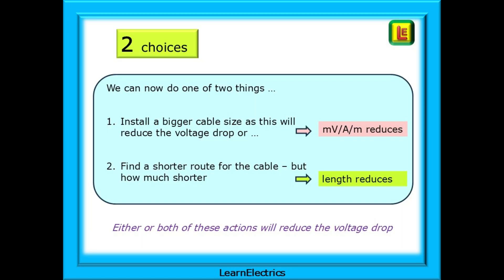We have two choices in order to find a solution. We can do one of two things. Either install a bigger cable size, as this will reduce the voltage drop, say from 4mm cable to 6mm. A bigger cable size will reduce the MVAM number. Or we could find a shorter route for the cable. But how much shorter? Can we calculate the new maximum length? If we reduce the length, we reduce the voltage drop. Either or both of these actions will reduce the voltage drop. We need to get below that magical 11.5 volts limit.